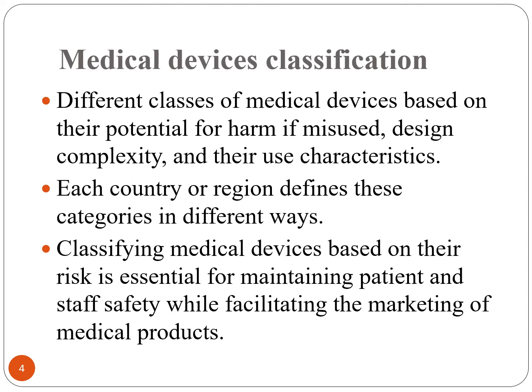What is the hazard to the patient? Devices are classified into class 1, which has less potential to harm the patient or the user, class 2, intermediate, and class 3, which has a high potential to harm the patient or the user if used by mistake or misused.